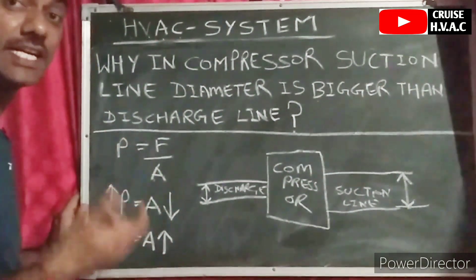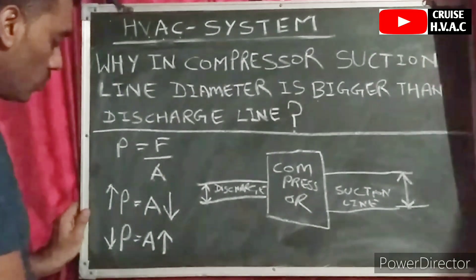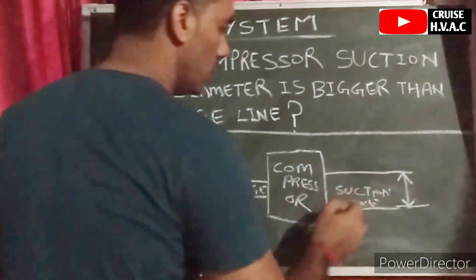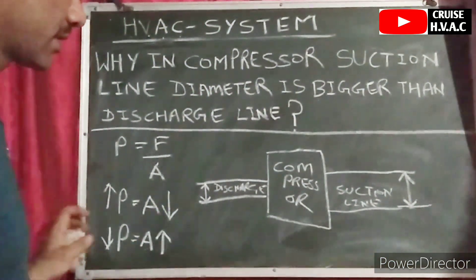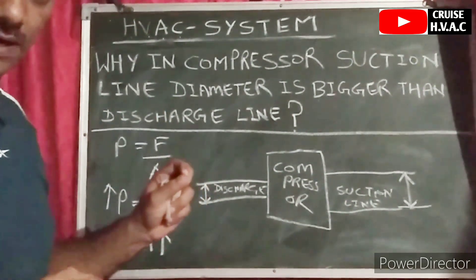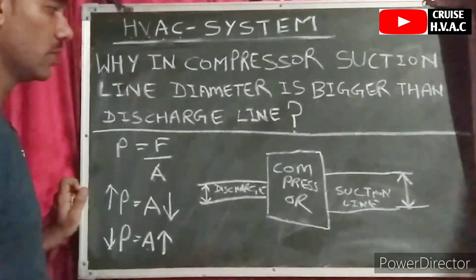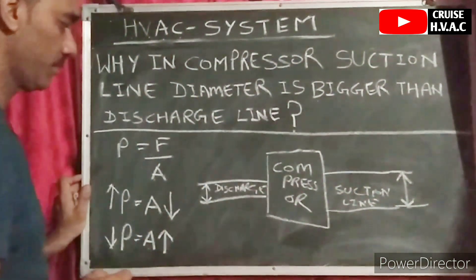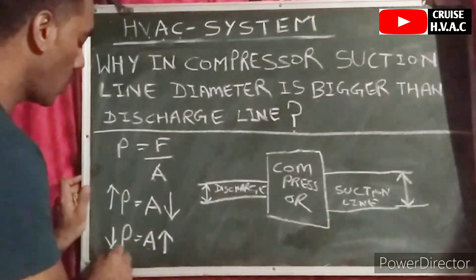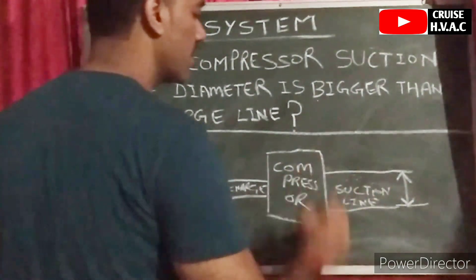When the refrigerant is in low pressure vapor form, its density is low. When the density of the vapor is low and the pressure is also low, the area is supposed to be bigger. This protects the compressor — because the compressor is made only to compress vapor refrigerant. If any liquid form of refrigerant goes inside the compressor, it will be completely damaged. So on the suction line, because the pressure is low, the area of the pipe is higher, and therefore the diameter of the pipe is higher.